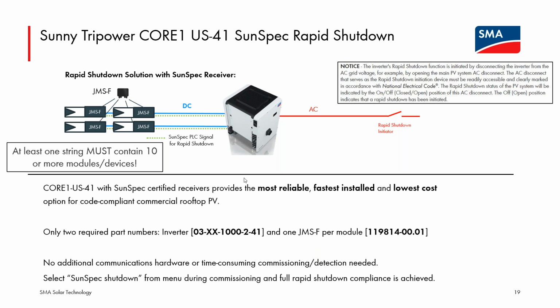Pairing this device with the CORE1 is all that is required. Again, the JMSF device is a one module input device, so there would be one of these for every module in the array. No matter how many modules you have, how many inverters you have, you would equip each with this device. Again, it's very simple to add on to these modules. You turn on the transmitter during commissioning, and you're done. That is all that you need to do.